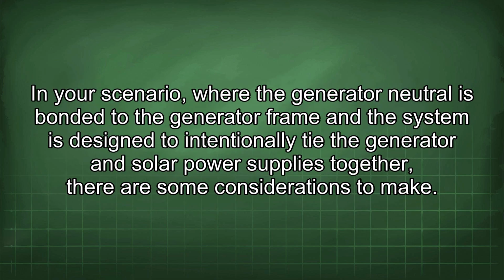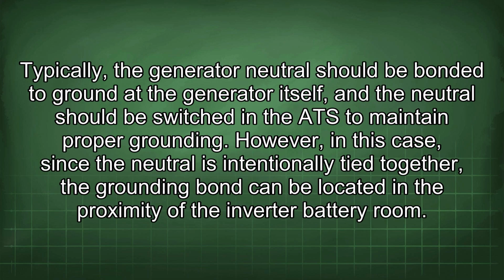In your scenario, where the generator neutral is bonded to the generator frame and the system is designed to intentionally tie the generator and solar power supplies together, there are some considerations to make. Typically, the generator neutral should be bonded to ground at the generator itself, and the neutral should be switched in the ATS to maintain proper grounding. However, in this case, since the neutral is intentionally tied together, the grounding bond can be located in the proximity of the inverter battery room.